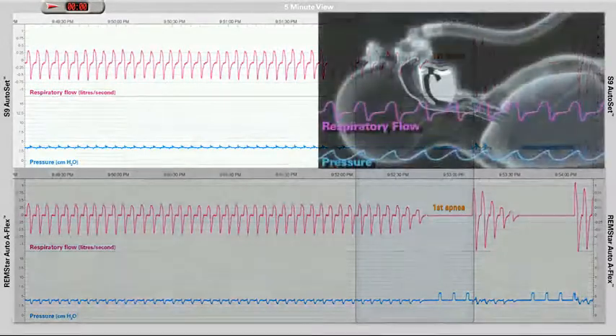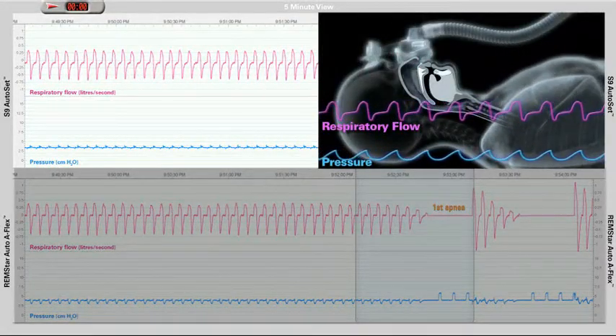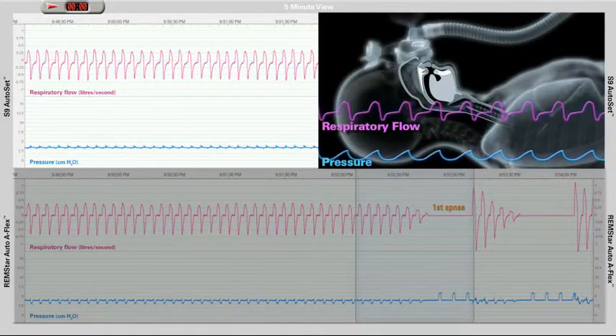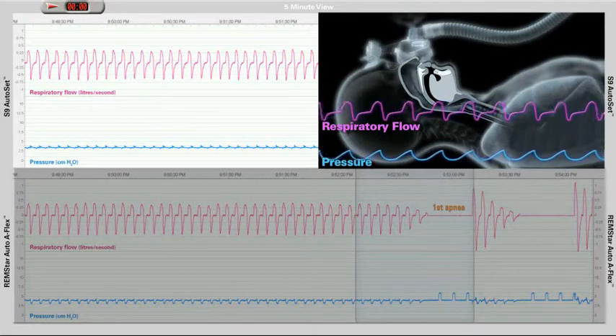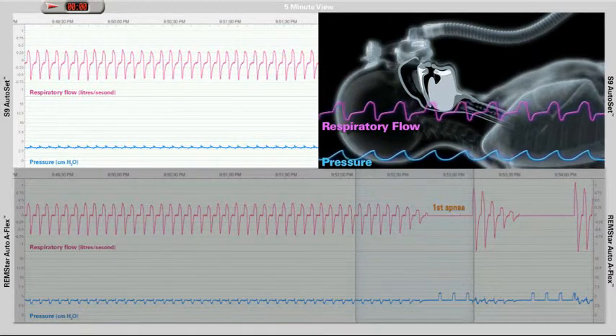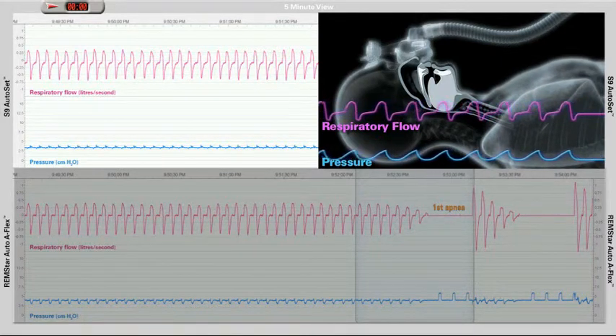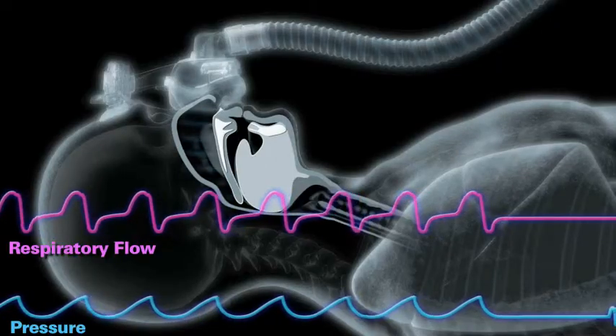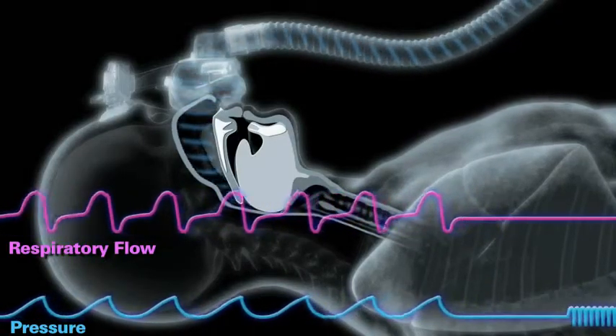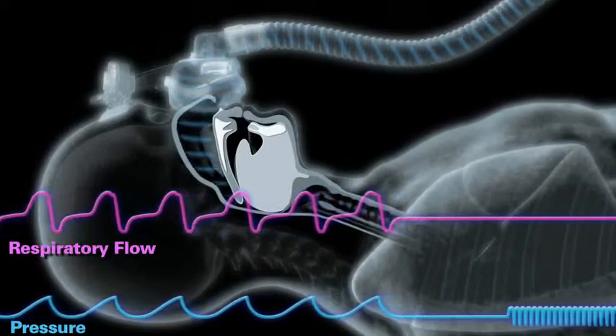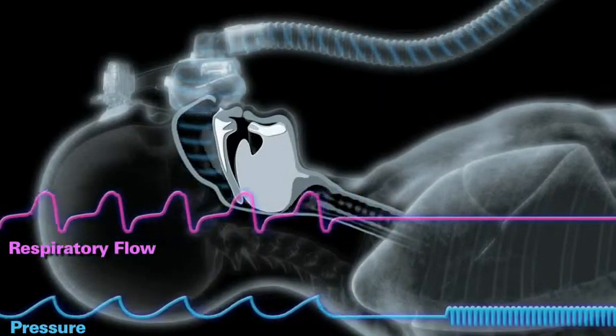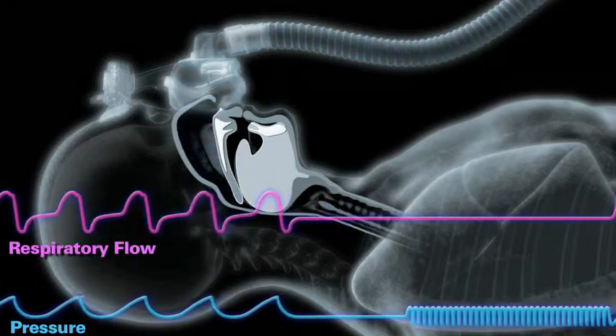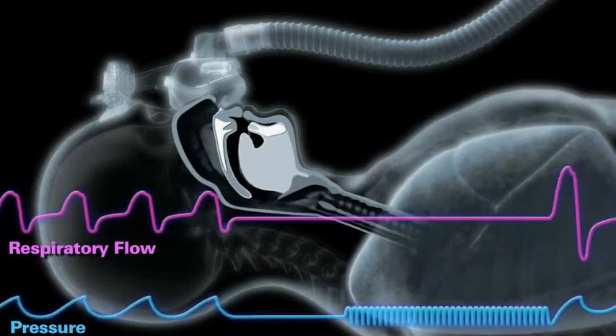ResMed's enhanced Autoset algorithm now incorporates the central sleep apnea detector. This uses a forced oscillation technique to determine whether the airway is open or closed during an apnea. Small oscillations in pressure are added to the current device pressure. The CSA detector uses the resulting flow and pressures to measure whether the airway is open or closed.